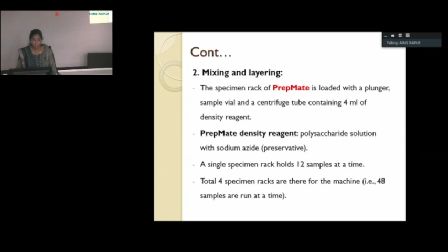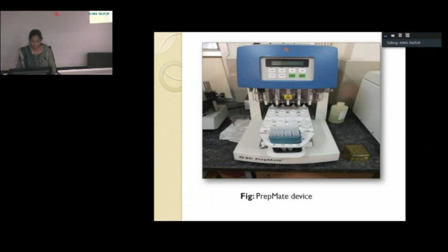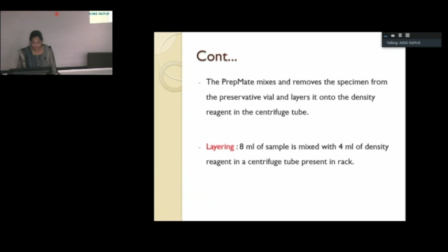This is the PrepMate device. Here we can see the sample rack where we can place the sample vial. Along with that, we also place the syringe and the centrifuge tube in which 4 ml of density gradient is added. The PrepMate mixes and removes the specimen from the preservative vial and layers it onto the density reagent in the centrifuge tube. In this layering step, 8 ml of sample is layered onto 4 ml of density reagent in a centrifuge tube present in the rack.